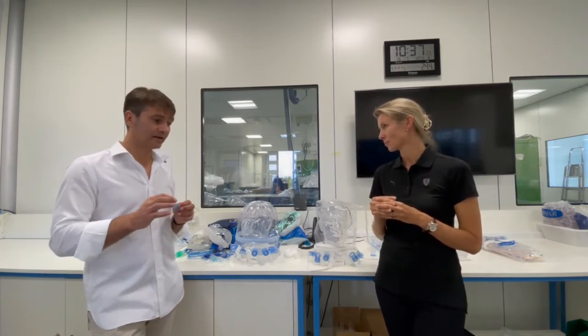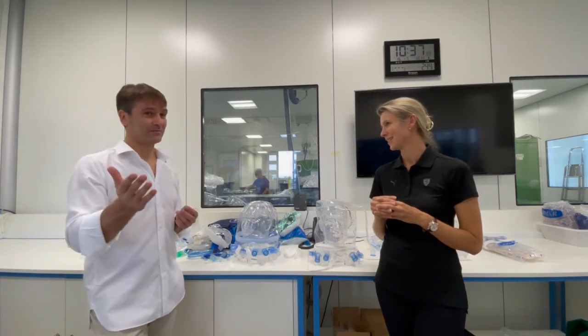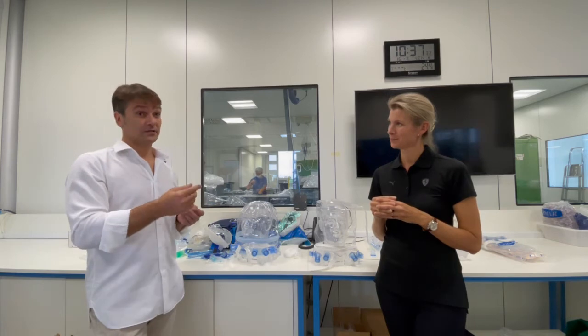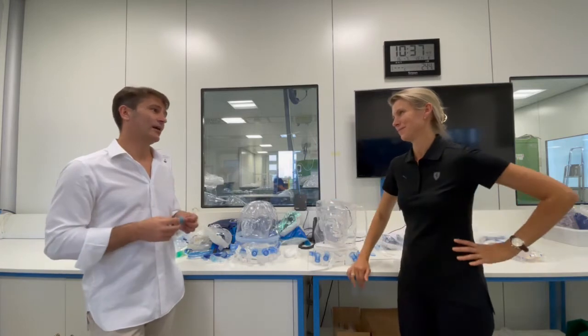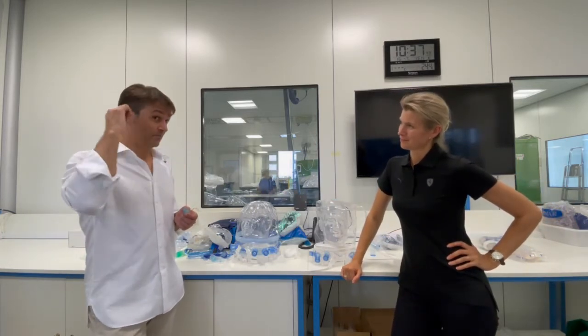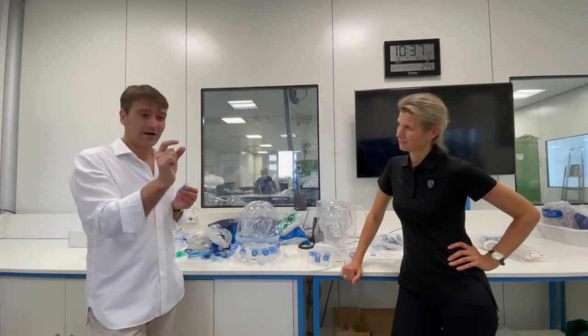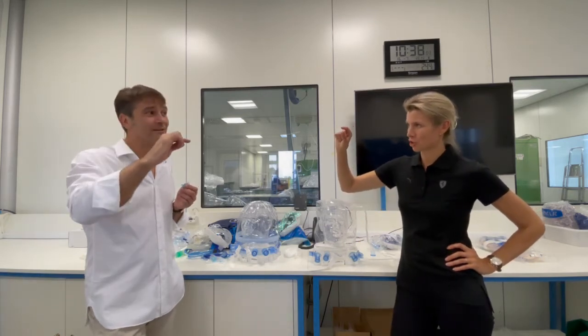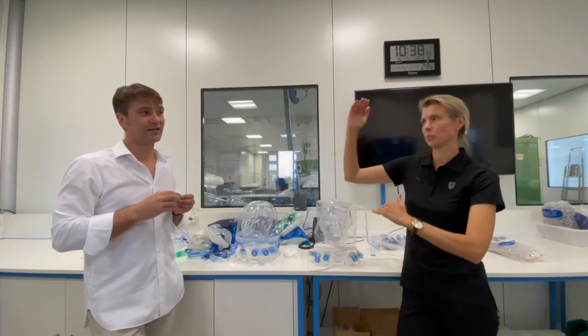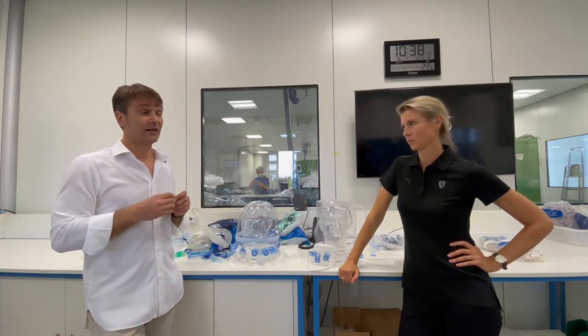You need to be there and adjust because a very high flow can solve a lot of problems, but it generates a lot of noise. Noise is one of the things immediately recognized by the patient, so if possible decrease the flow a little bit and have the same effect. Start with a high flow. See if the pressure is stable on the manometer, then decrease a little bit — it will still have a little fluctuation. When you see it moving, that's the point where you can stop, but not too much — otherwise the pressure inside becomes unstable and the patient will feel a lack of air.